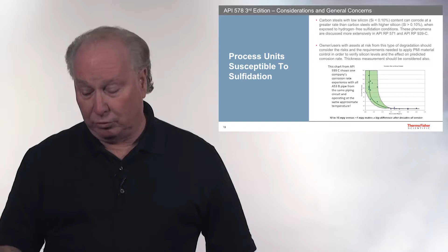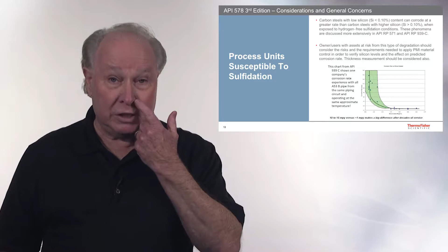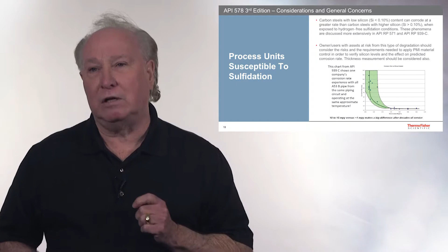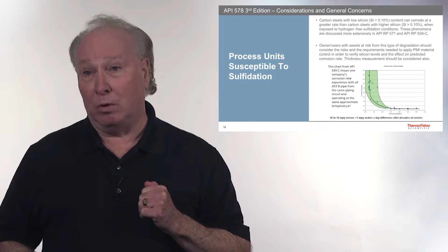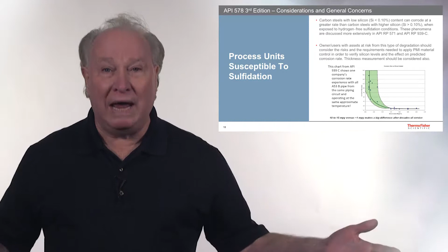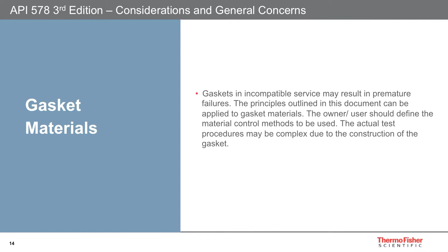API RP 571 talks about that corrosion mechanism, but there's a whole document on sulfidic corrosion called 939C. API 939C and 571 both cover that. The big problem we had pre-1985 is A53 pipe had no spec for silicon in it, while A106 pipe has a specification of a minimum of 0.10%. So we still have pipes from 30 and 40 years ago out there that are corroding very fast. That's a big one.